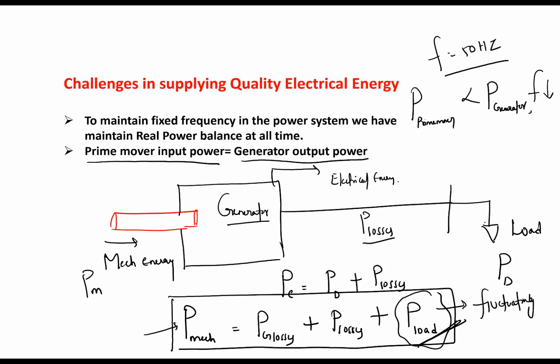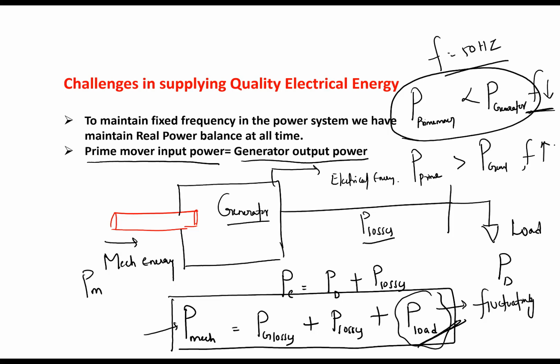Many people think that the RPM with which we are rotating decides frequency. Absolutely right. But who governs that RPM? Why will the turbine slow down or accelerate? The turbine will accelerate when the load on it is less. When the load is more than what it can supply, the turbine will decelerate. That means its speed will fall, and then the frequency will reduce. When prime mover power is greater than what the generator requires, then frequency will overshoot. The turbine will accelerate. Understood? This is one challenge. Any doubt you can ask.